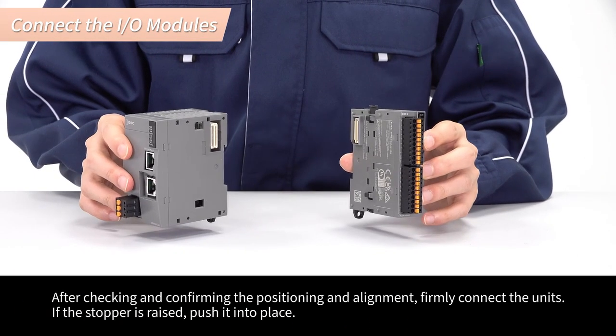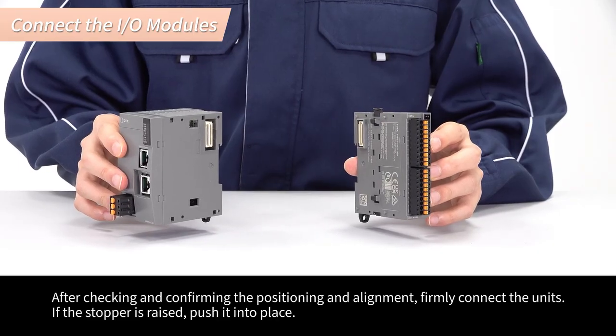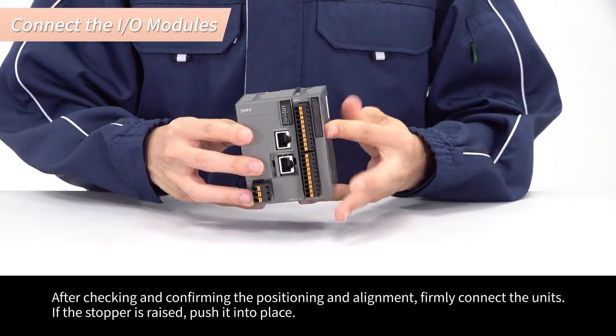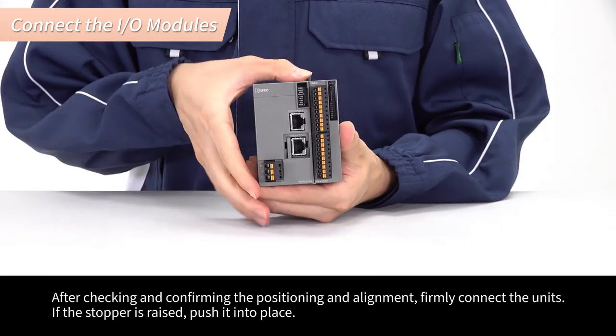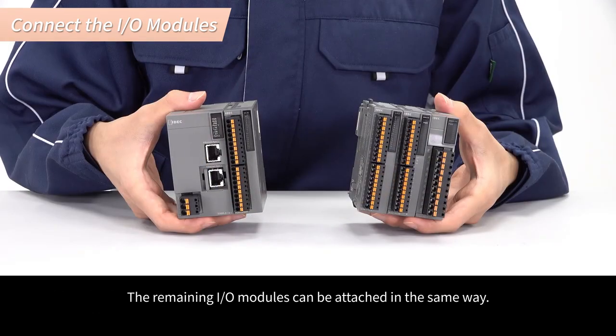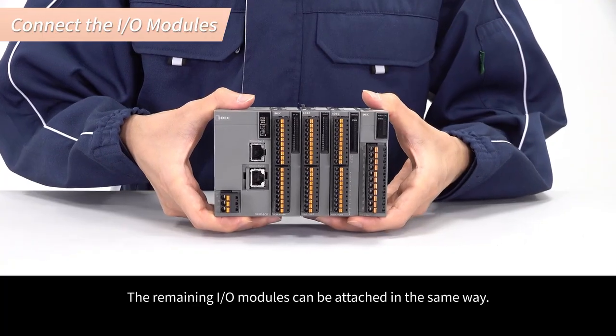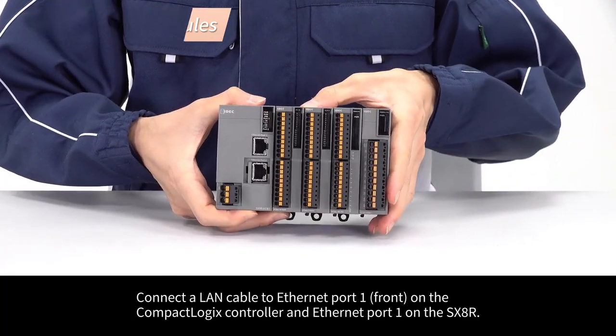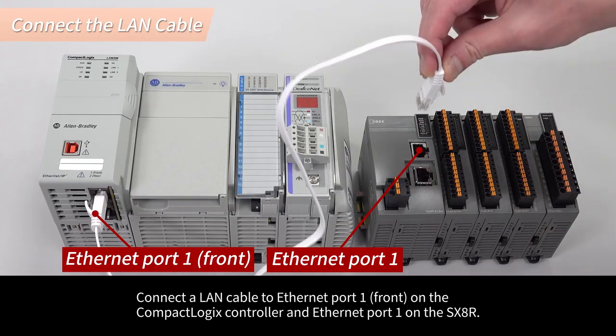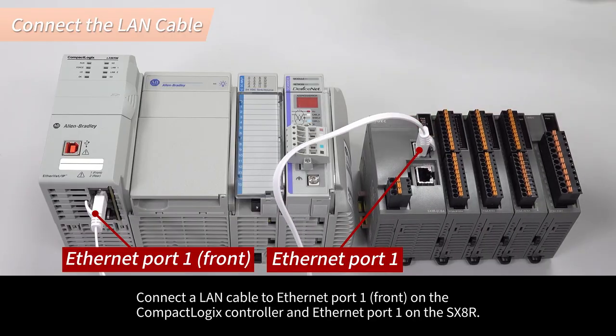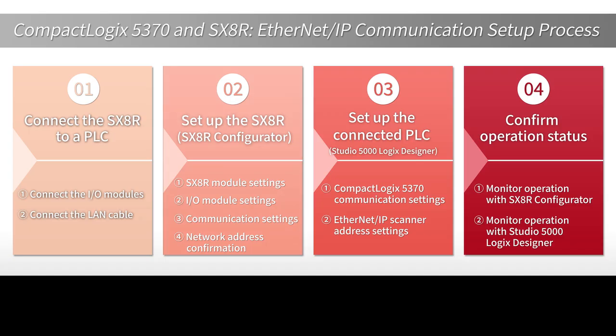After checking and confirming the positioning and alignment, firmly connect the units. If the stopper is raised, push it into place. The remaining I/O modules can be attached in the same way. Connect a LAN cable to Ethernet port 1 front on the CompactLogix controller and Ethernet port 1 on the SX8R.